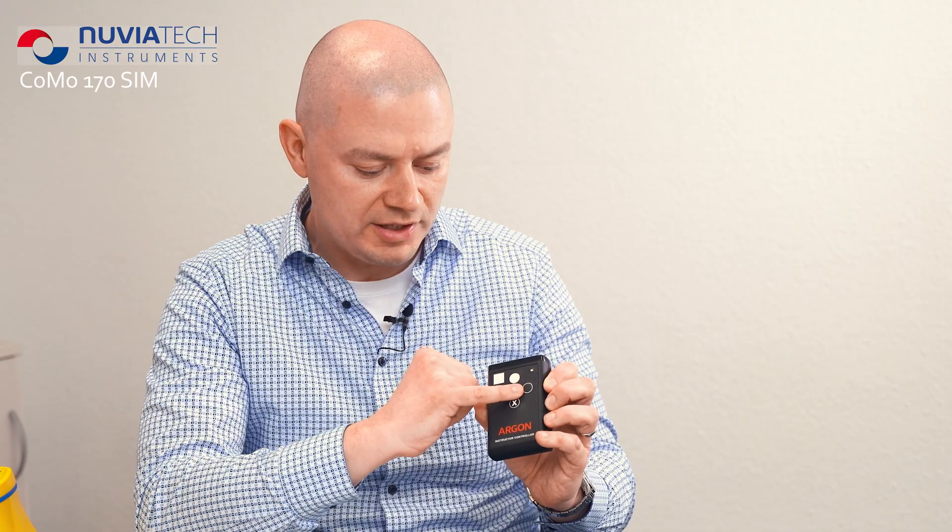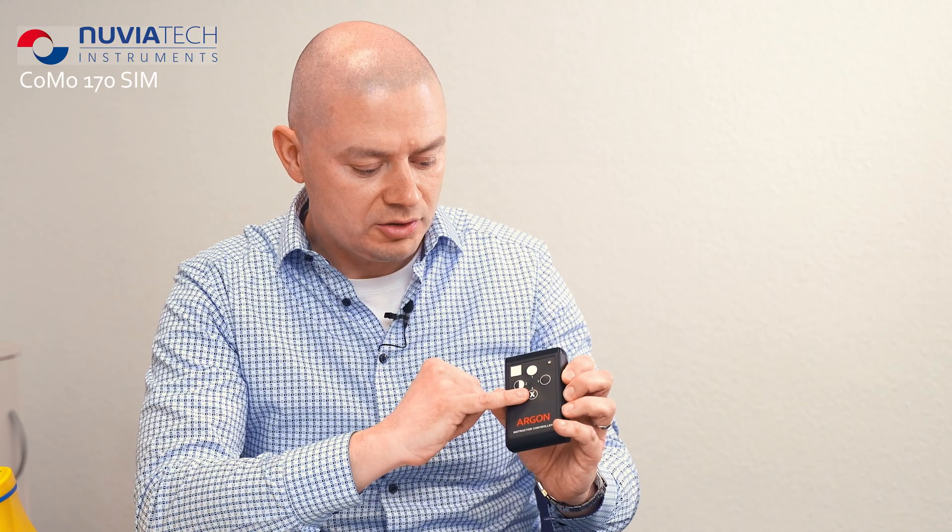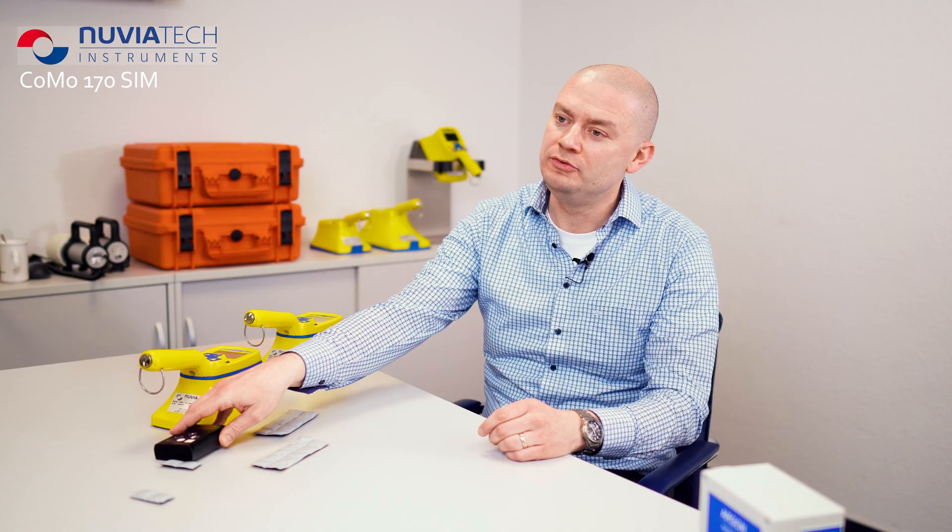Button number three serves as a zero value, so if the decontamination has been successful, you can press button number three. Button number four is used as a detector error. All in all, the CoMo 170 SIM is a perfect training device if you do not have real radioactive sources. Thank you for watching our presentation and please subscribe.